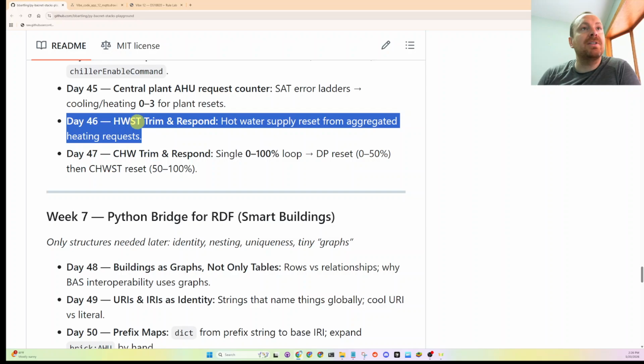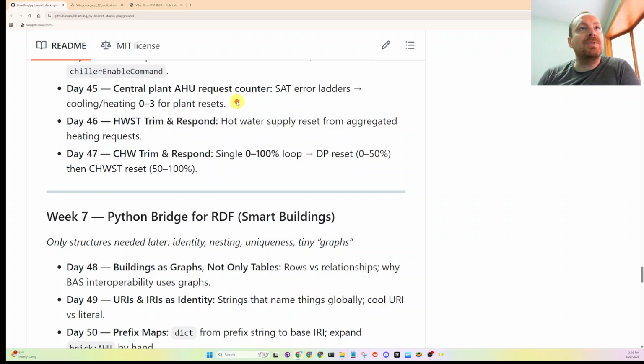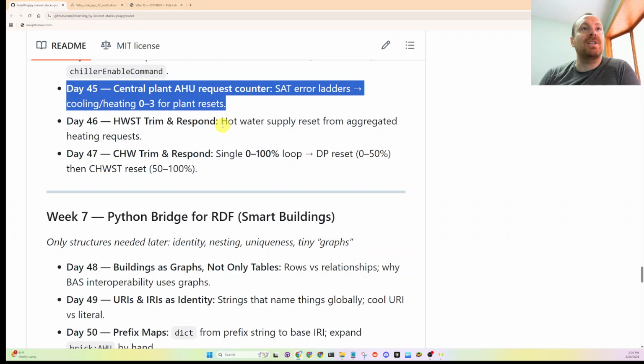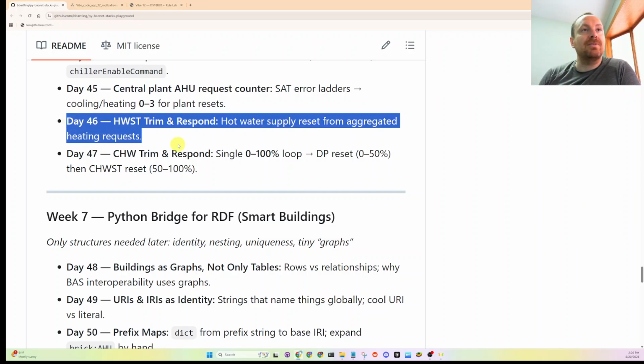The hot water plant trim and respond is generated from air handling unit requests for heat, and then it resets the chiller or the boiler plant hot water set point. It's kind of cool, it's working, no complaints on the building yet.